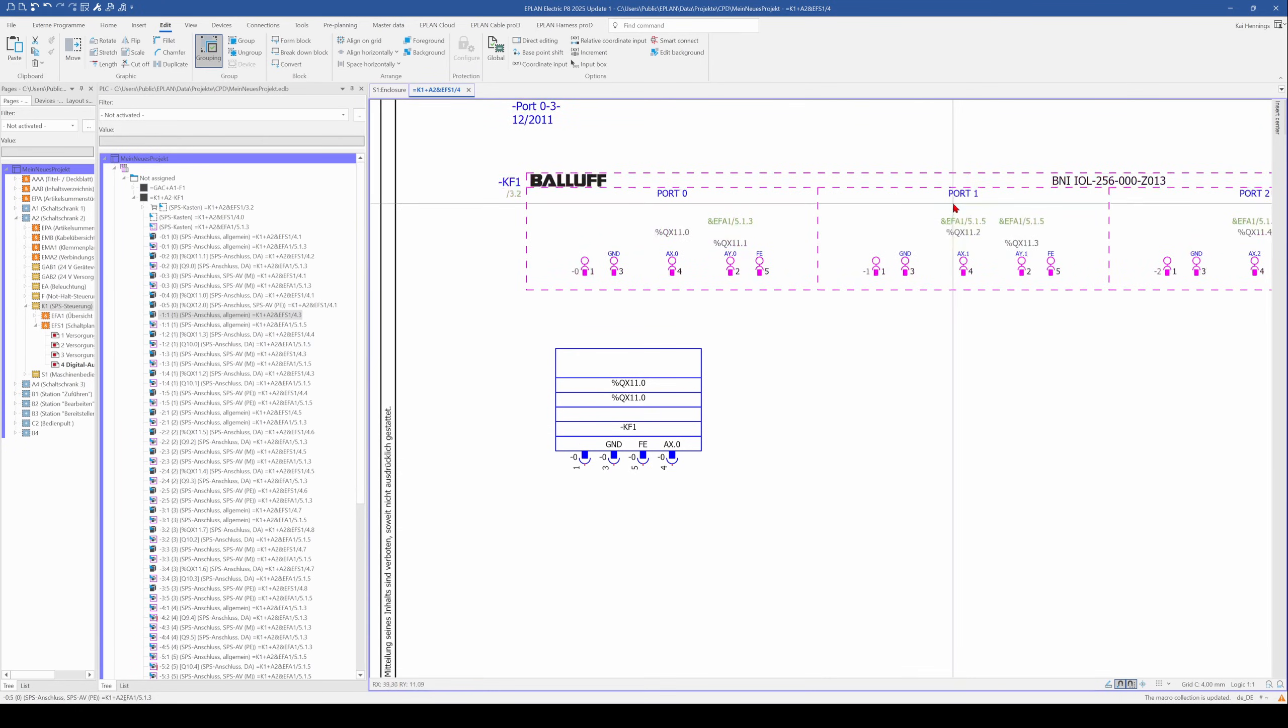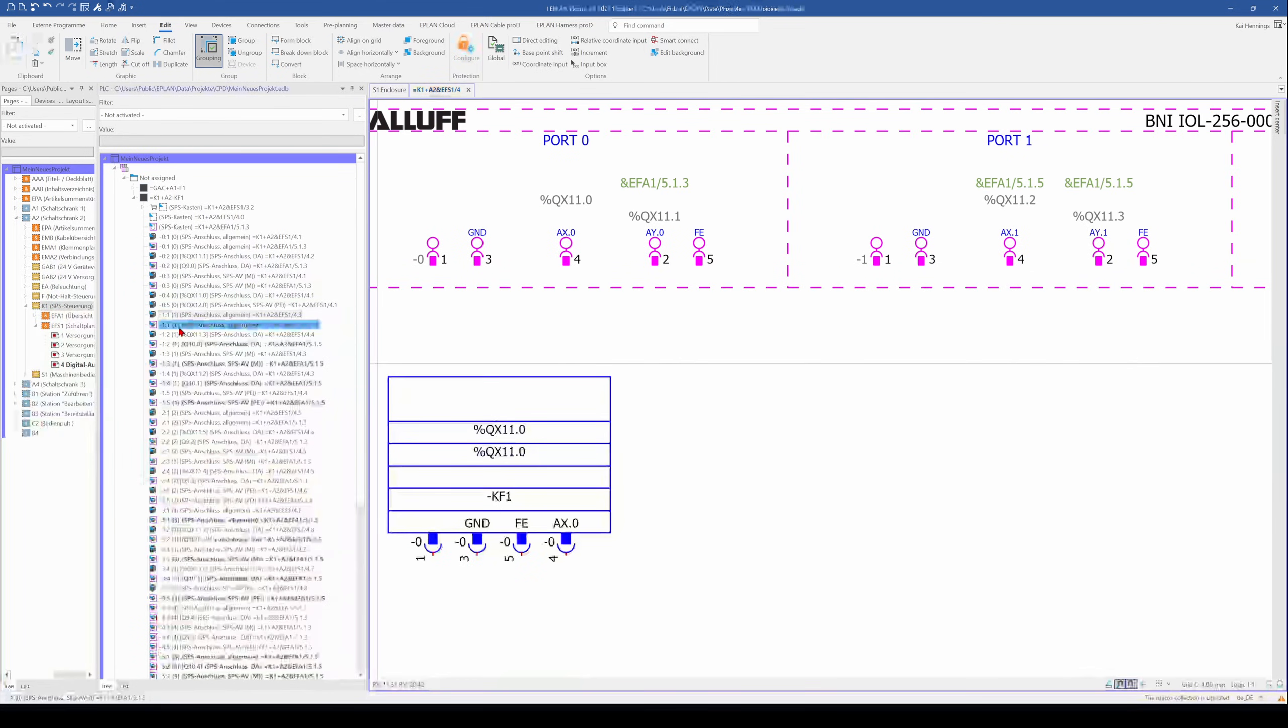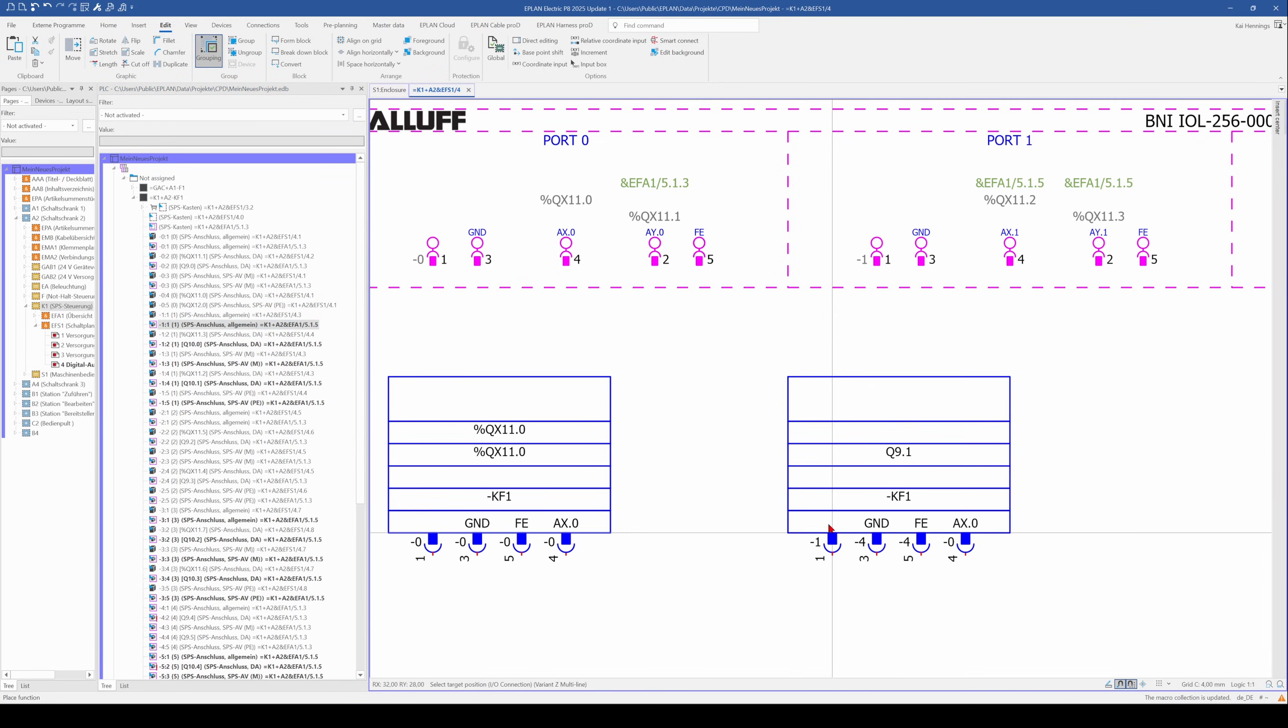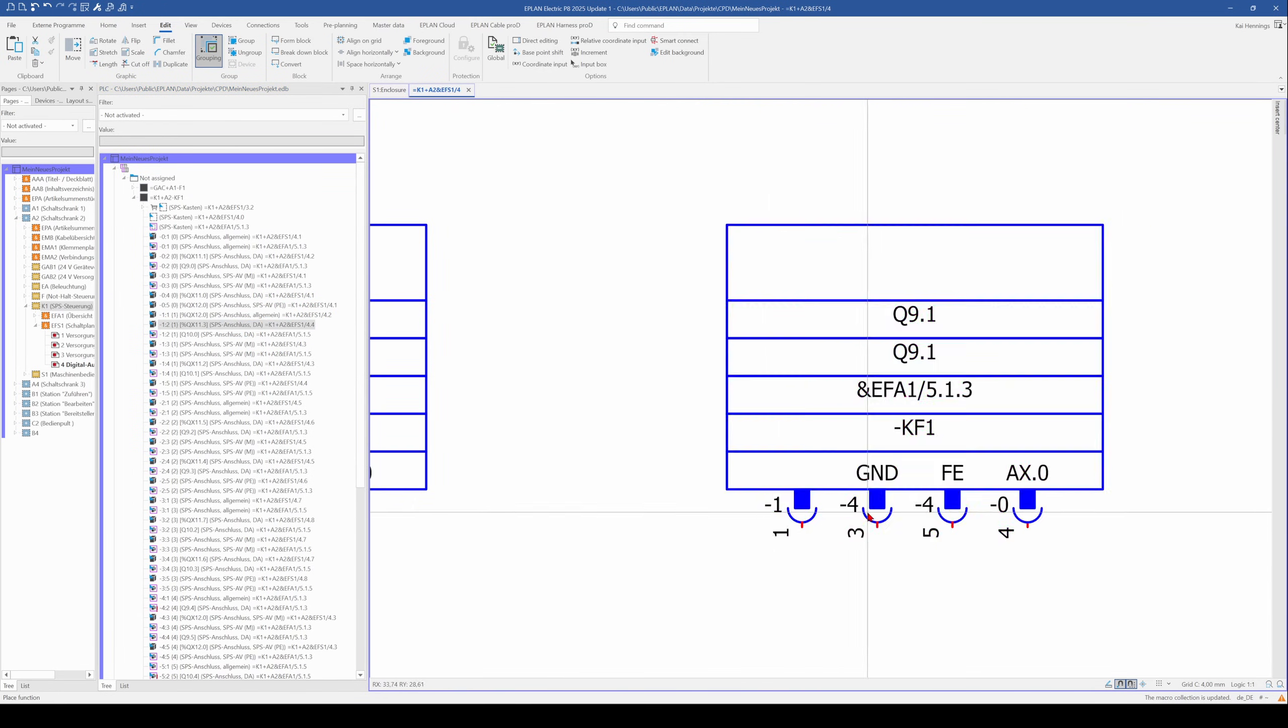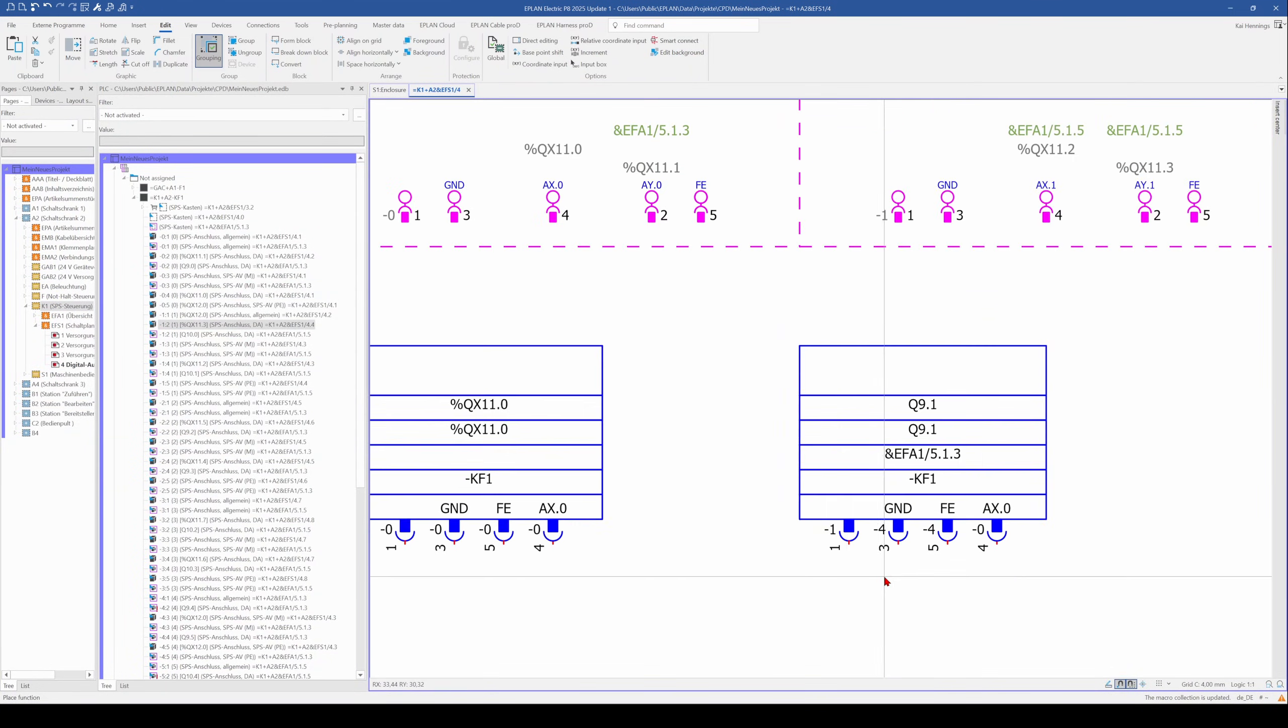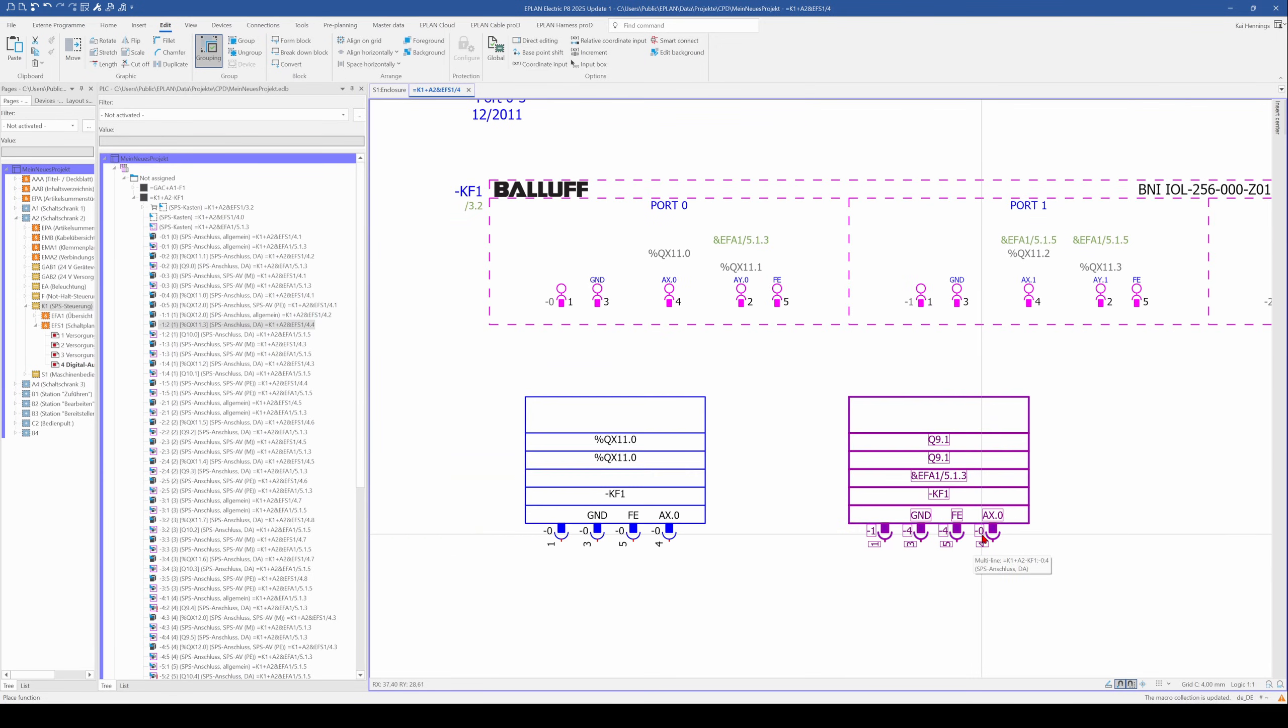This is the macro and when we want to have now the second port, port number one, which goes to plug one, we see it also here on our PLC navigator. We can use it here and we have it on our cursor. It's placed for connections, but as you can see here, this is from plug number one, this is from plug number four and this is from plug number zero, so it's totally wrong.